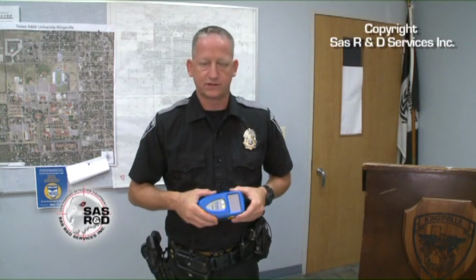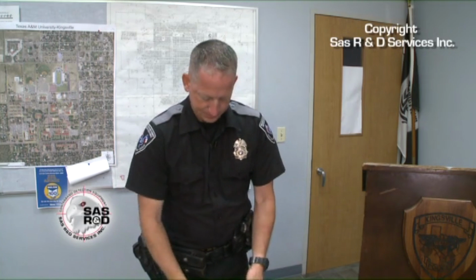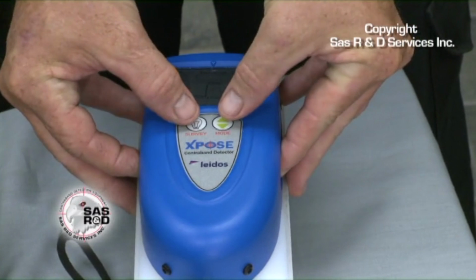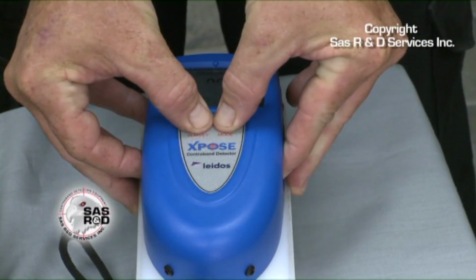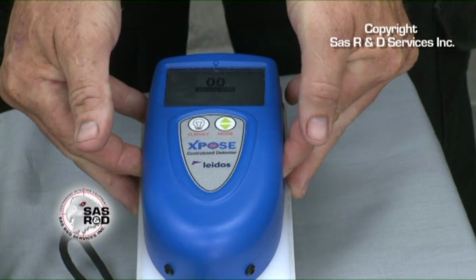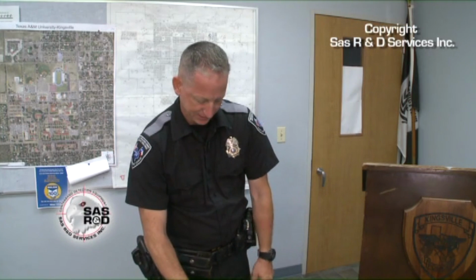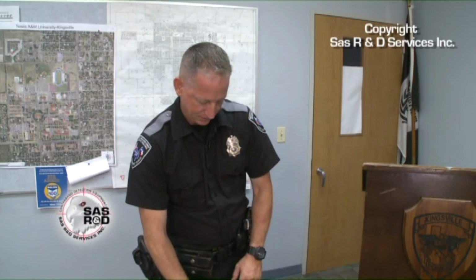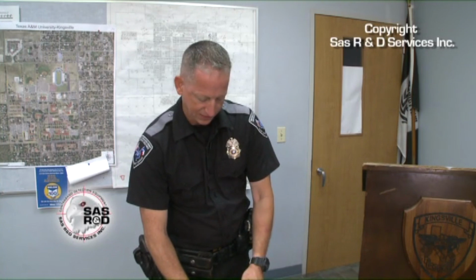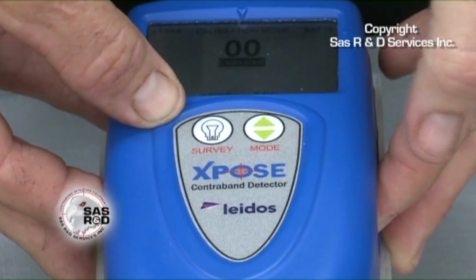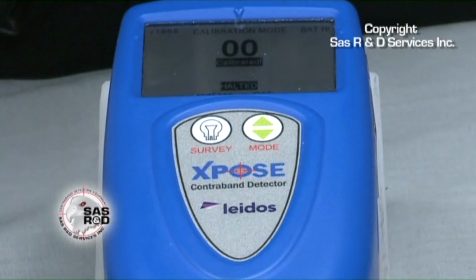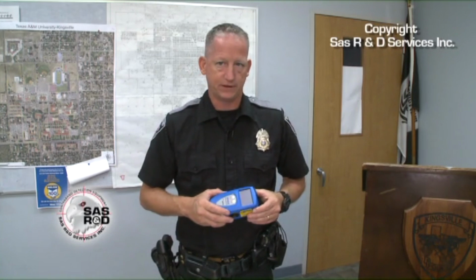To calibrate the Xpose densimeter, place the enclosed calibration block on a firm table. Place the Xpose on top of the calibration block. Press the left and right buttons at the same time while holding the survey mode and mode buttons at the same time. Release. This will be done for approximately 10 seconds. The display will now tell you that you have successfully completed the calibration and will ask you to save or abort. Press save and release the two side buttons. Calibration is complete. Calibration is only necessary about every 6 months.